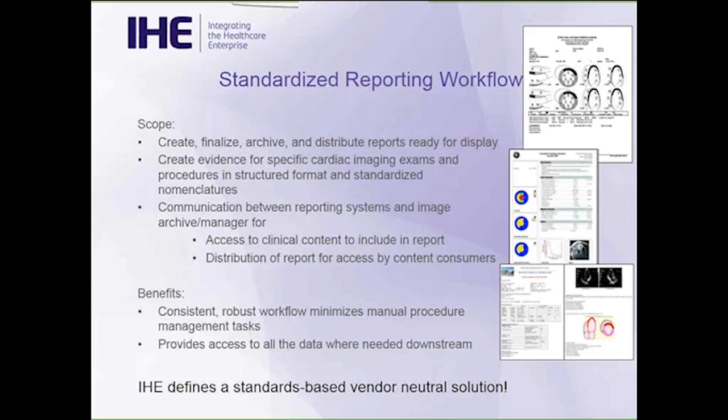IHE Cardiology has also created a displayable reports profile focusing on the creation, revision, transmission, and reading of display-ready reports. And since there's a lot of graphics and other information in there, that's really important. This cardiology-specific profile supports PDF as well as CDA documents using HL7 v2 messaging for exchange of those reports.